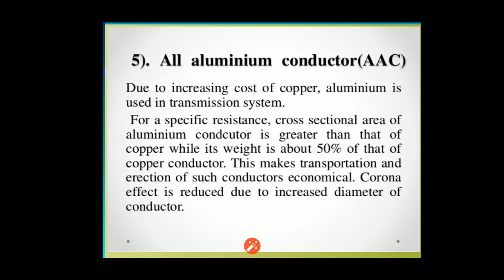Fifth, the all-aluminium conductor. Due to increases in the cost of copper, aluminium is used in transmission lines. For a specific resistance, the cross-sectional area of the aluminium conductor is greater than that of copper, while its weight is about 50 percent of that of the copper conductor. This makes transportation and erection economical, and the corona effect is also reduced due to the larger diameter.